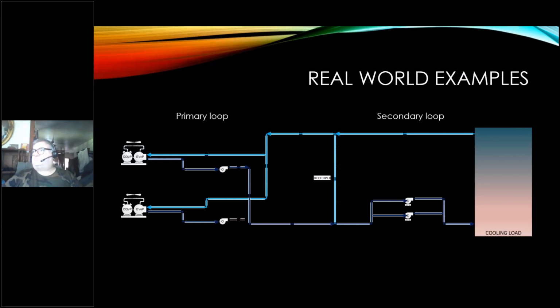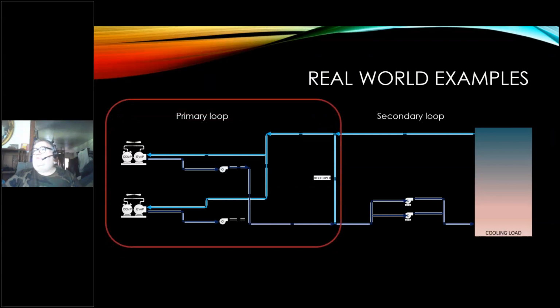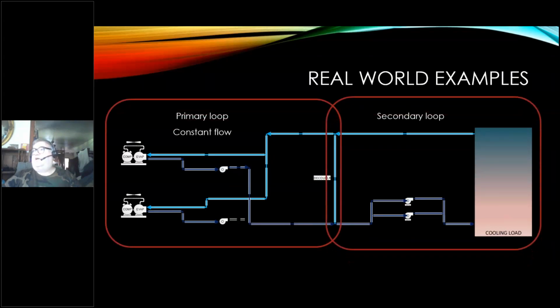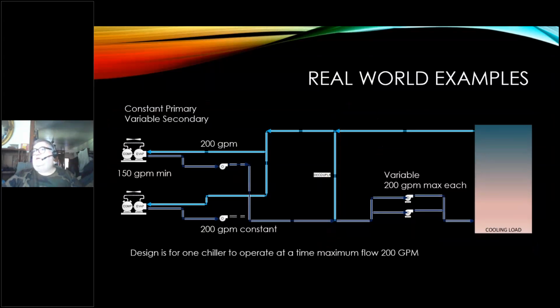Another example, we've got a primary loop and a secondary loop, with pumps on each side. In this case, the primary loop is constant speed, but my secondary loop is variable flow. The design flow is only 200 GPM for the cooling load, so the chillers are redundant. The pumps on the primary loop are 200 each, but I also have a minimum flow required on the chiller of 150. So the question came up, why don't we put drives on those pumps on the primary side? Well, I've only got 50 GPM to work with. If I go below 150, my chiller shuts down.